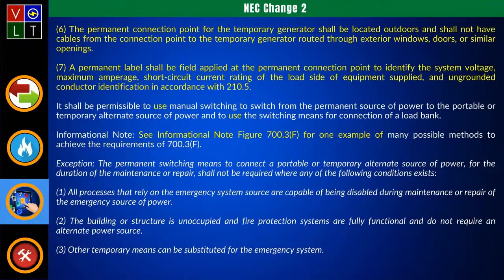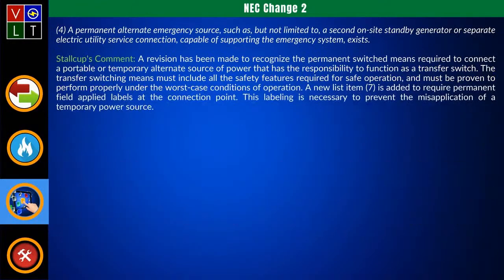Okay. Nice. So all they did here is look at where I'm dealing with generators and make sure you recognize that we have requirements in place for the permanent switching means that's required to connect a portable or temporary alternate source of power. The reason is that the permanent switching means we're putting in has a responsibility to function as what? A transfer switch. Yes, sir. That's why it has to be in there. So if that is the case, then that transfer switching means has to include all of the safety features that are required for what?